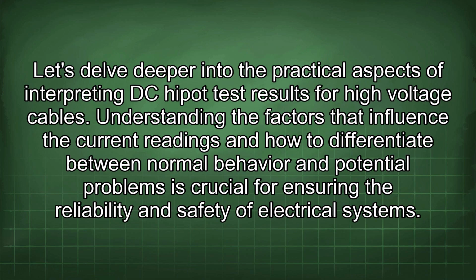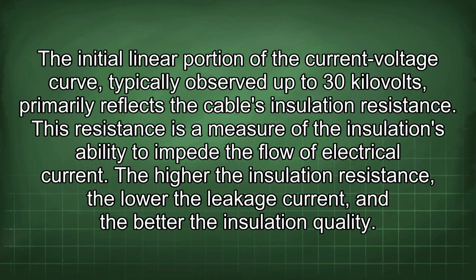Let's delve deeper into the practical aspects of interpreting DC hipot test results for high-voltage cables. Understanding the factors that influence the current readings and how to differentiate between normal behavior and potential problems is crucial for ensuring the reliability and safety of electrical systems. The initial linear portion of the current voltage curve, typically observed up to 30 kV, primarily reflects the cable's insulation resistance. This resistance is a measure of the insulation's ability to impede the flow of electrical current. The higher the insulation resistance, the lower the leakage current, and the better the insulation quality.